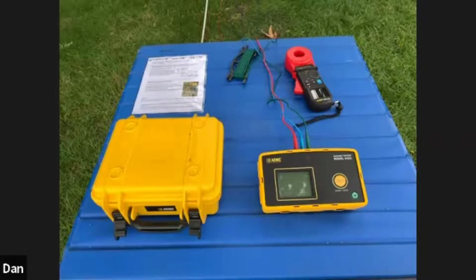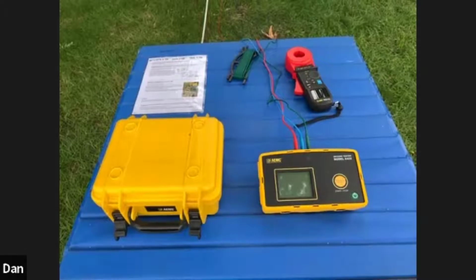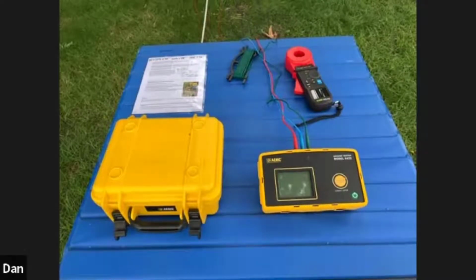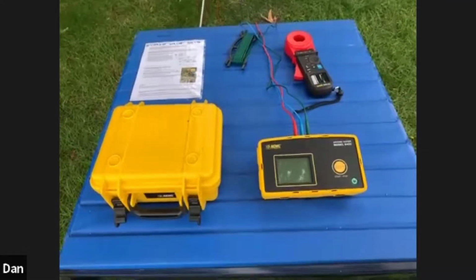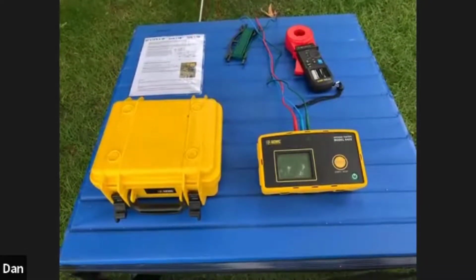Just keep in mind though, if you're in an area having trouble getting good low grounds, the ground plates have a lot more copper surface area touching the ground. There's a percentage number—it's quite astounding how much more copper surface area there is on a ground plate, whether it's a 4-foot or the 8-footer, compared to a ground rod. So sometimes when you're in those bad spots and can't get a ground, you might really consider the ground plates. It might be the only option.